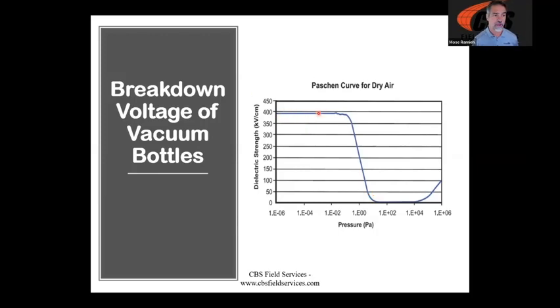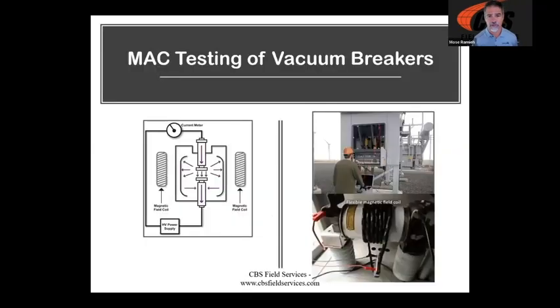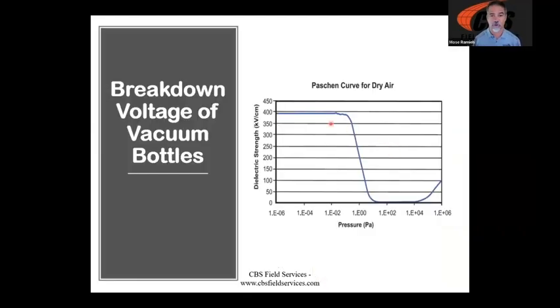And you can see that I'm a go. I mean, I'm going to pass this test. I'm going to pass this test all the way until I'm basically going towards atmospheric pressure. So we want to keep that in mind. And once again, we've got a test called a magnetronic atmospheric condition test, or the MAC test. It not only applies a voltage, but a magnetic field around the breaker where we can measure that ion gap and then estimate the pressure that's in the bottle. So once again, we can begin to tell you where you're at on this curve so that you can take action.